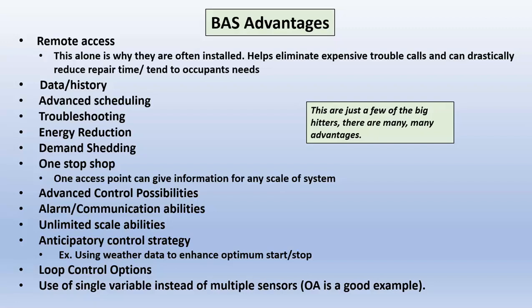But demand shedding, basically you're taking an input from the utility or from your own power meter, and it's telling you, you've hit a point where you're going to start paying too much money, and you can start slowing down VFDs, turning things off, raising temperature set points. There's a lot of things you can do to reduce your demand. Or you can do what's demand rolling, where you just shut off some things every 10 minutes. You rotate through. There's a lot of things. Rolling load, I think.